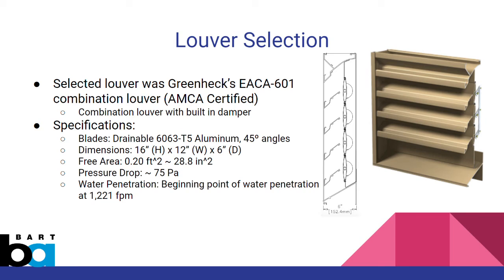The free area associated with these dimensions is 0.2 feet squared, or 28.8 inches squared. The pressure drop created by the louver's free area velocity when the train is traveling at its cruising speed is found to be about 75 pascals. The beginning point of water penetration is at 1,221 feet per minute.